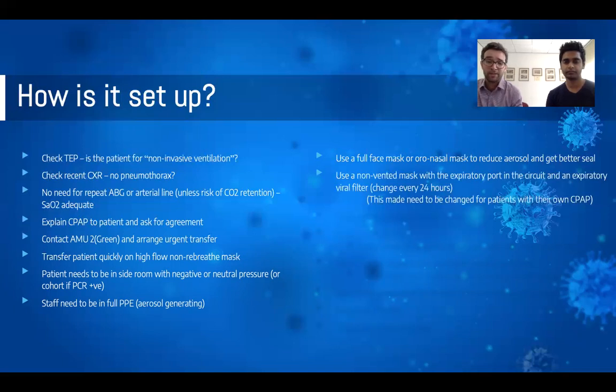Again, little technical aspects which Emma will show you in a second, that the masks we're now using are non-vented, again to reduce the aerosol exposure around the room, and the expiratory port is built into the circuit, so the patient breathes out into the tube rather than into the room, and that goes via a filter, which is really important here to protect the staff and the machine. It is possible to damage the machines if the filters aren't used properly, and this puts them out of action and is quite expensive to fix.